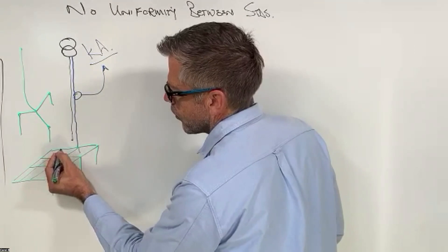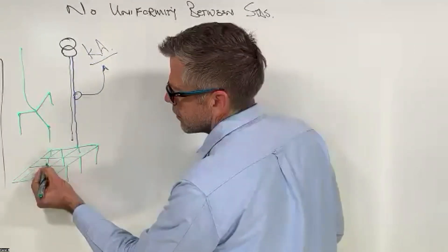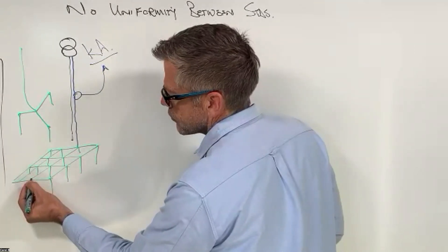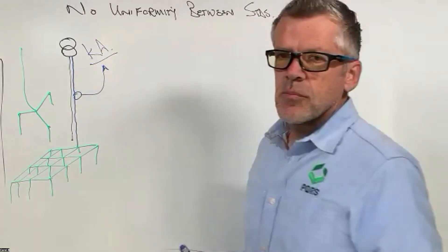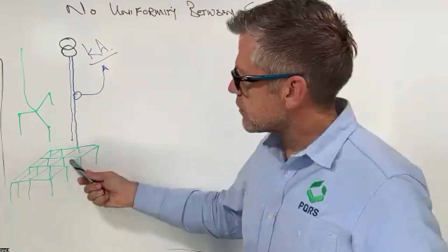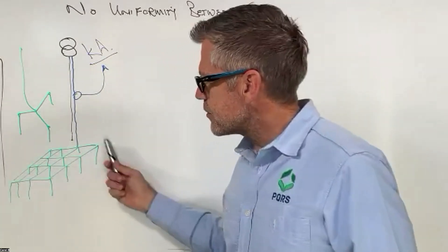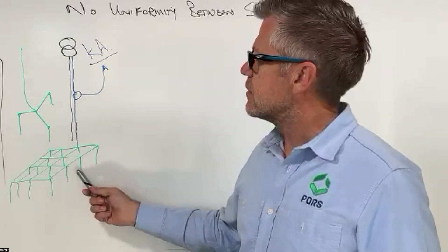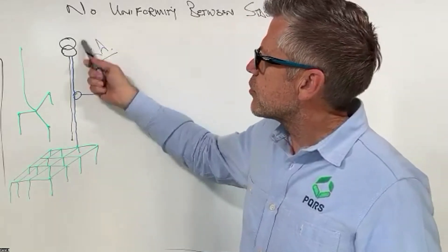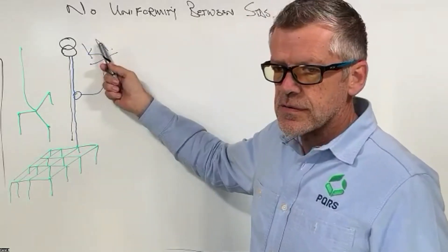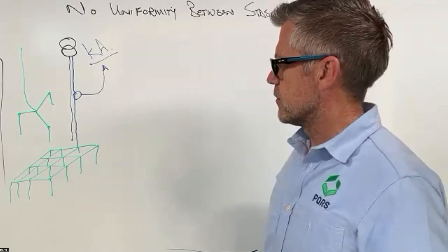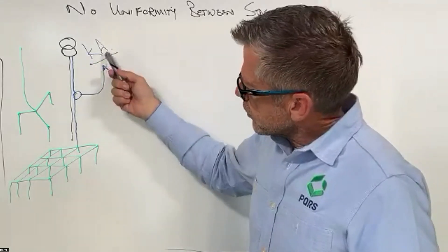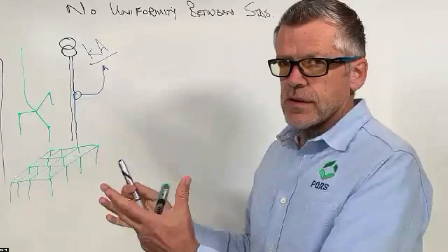The copper wire or the net, if I want to call it that, is welded together and each one of those points have a spike connected to it. These arrangements are created bearing in mind what the fault current value is coming from the transformer.